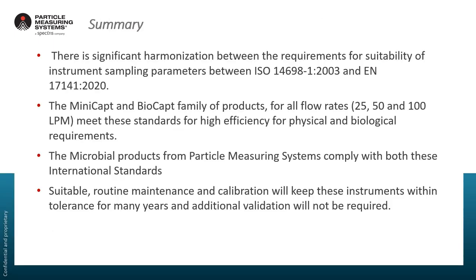In summary, there is a lot of harmonization between the requirements of ISO 14698 and EN 17141. The MiniCapt and BioCapt families of products for all flow rates meet those standards and demonstrate high efficiency for physical and biological requirements. Microbial products from Particle Measuring Systems comply with both of these international standards, and with most instruments, suitable routine maintenance and calibration will keep them within tolerance for many years without requiring additional validation.